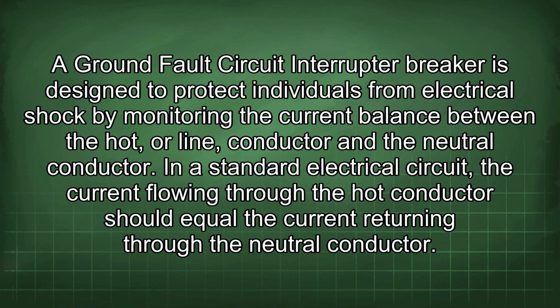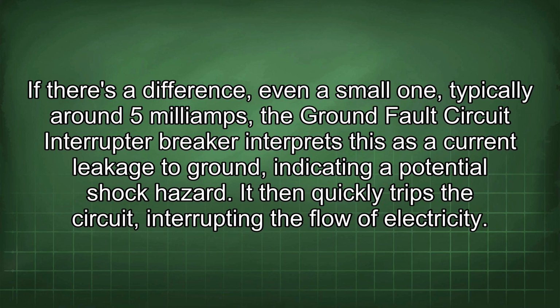In a standard electrical circuit, the current flowing through the hot conductor should equal the current returning through the neutral conductor. If there's a difference, even a small one, typically around 5 mA, the ground fault circuit interrupter breaker interprets this as a current leakage to ground, indicating a potential shock hazard. It then quickly trips the circuit, interrupting the flow of electricity.